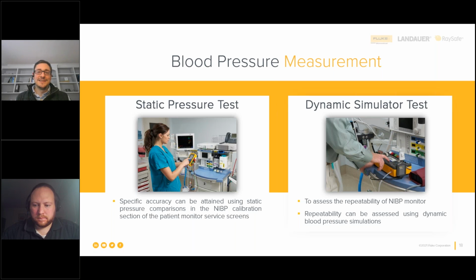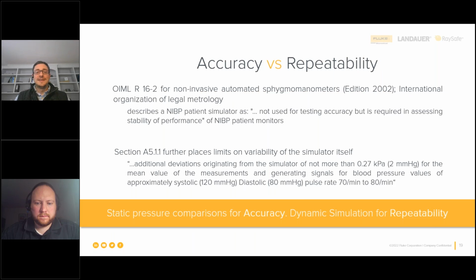So dynamic accuracy, which is more closely related to the patient itself, is really hard to nail down. OEMs have done this using statistical sampling and the analysis of clinical measurements, but there really is no standard in terms of how to assess dynamic blood pressure, especially in terms of accuracy and repeatability. So patient simulators have really been used in the past to mimic that dynamic nature of NIBP, because it is quite repeatable, but it might not be precisely clinically correct, let's put it that way, when you compare it with a live patient.